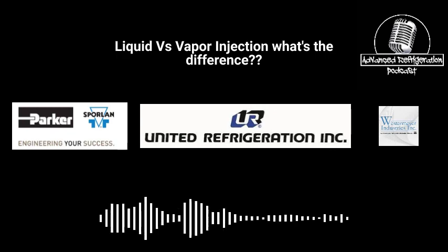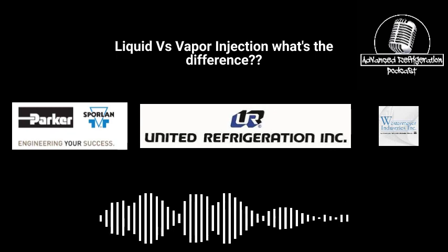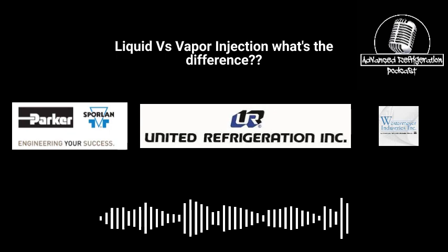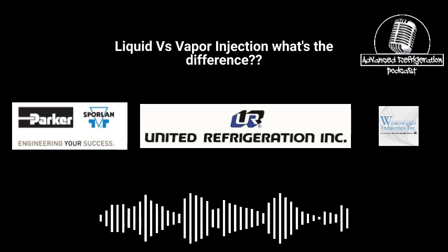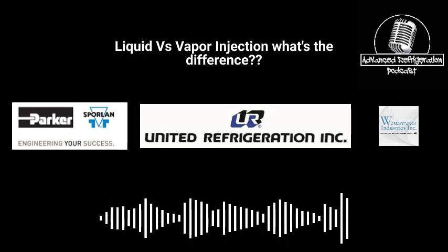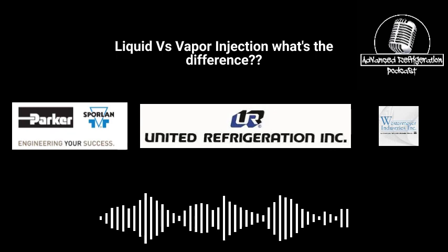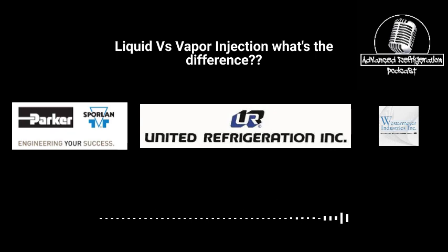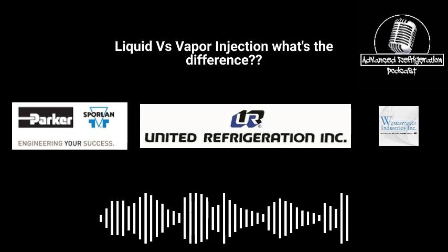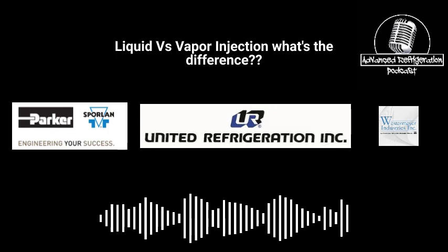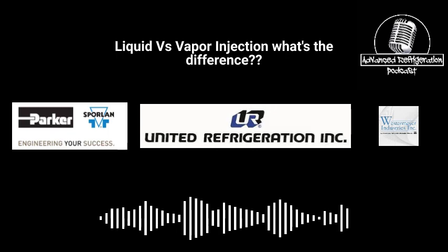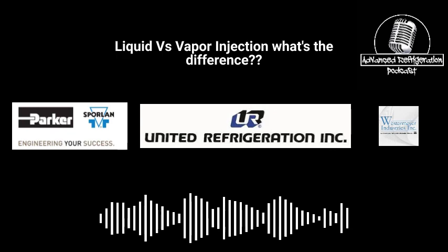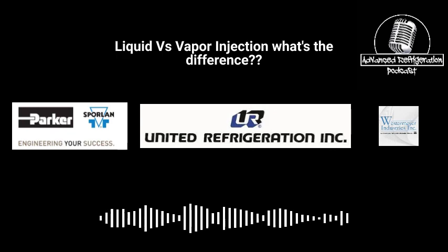Now, a big thing that guys miss is you do not want the subcooler cycling on liquid temperature on anything that runs vapor injection. That subcooler needs to have 24 hours, 7 days a week runtime. The only time that subcooler should shut off is if the rack shuts off. That is the number one thing I see guys mess up the most with vapor injection compressors, especially at the Bullseye store. You'll pull up there and you look at the top of the compressors and the paint's peeling off the top of them.